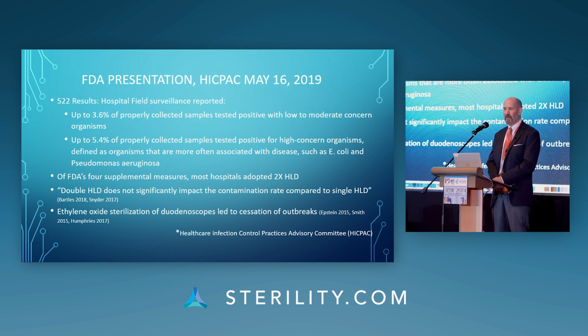Of the FDA's 4 supplemental measures, the one that most hospitals had adopted was dual high-level disinfection cycles. So these would be back-to-back or double cycles of high-level disinfection. And FDA discovered that multiple cycles of high-level disinfection were no more effective than a single cycle of HLD in eliminating these organisms. Also significantly, ethylene oxide was one of the supplemental measures that FDA recommended. And very significantly, every hospital that adopted ethylene oxide sterilization ended their outbreak immediately.